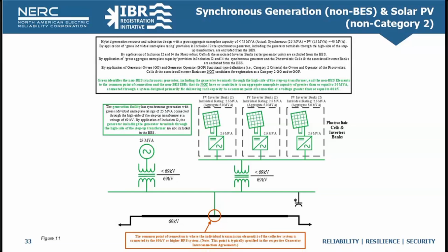Again, the first step in this example is to evaluate based on applying the BES definition to the facilities. Therefore, by application of the BES definition, with a connection voltage of 69 kV, the 25 MVA synchronous generator and the 15 MVA solar component are excluded from the bulk electric system.